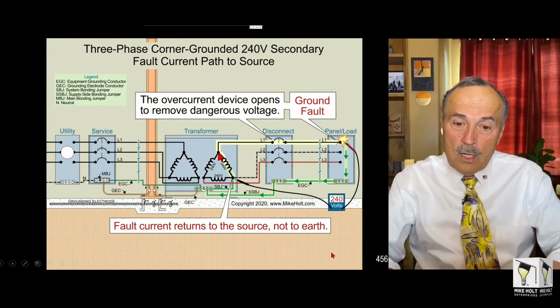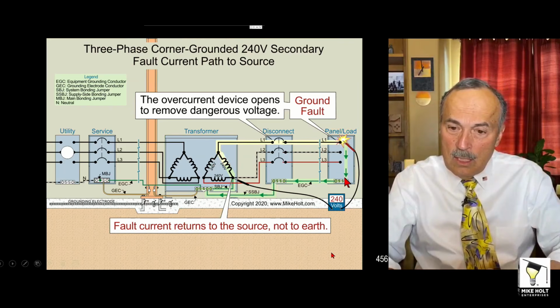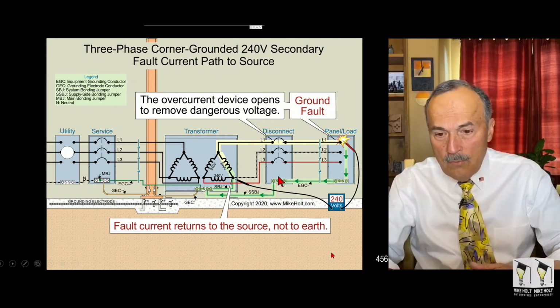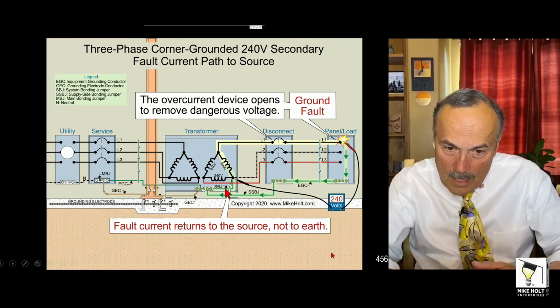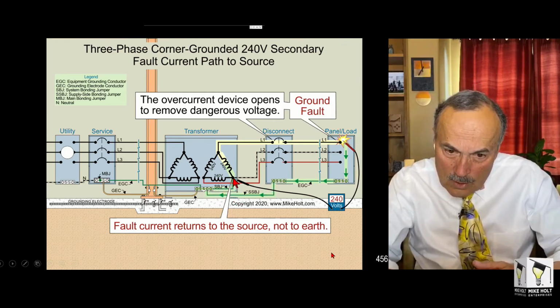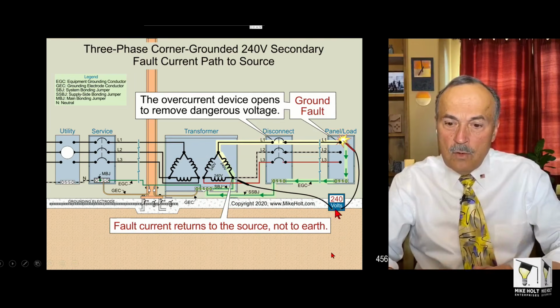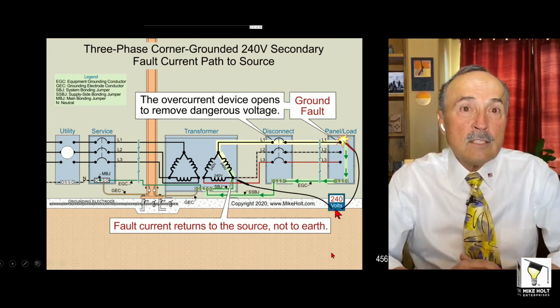Okay. Fault current leaves the 240 volt systems, travels along the effective ground fault current path. System bonding jumper goes up inside here, bada bing, bada boom, 240 volt fault, opens a protection device.